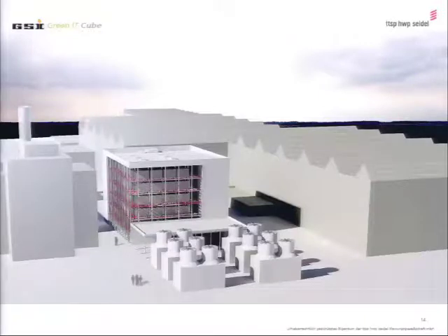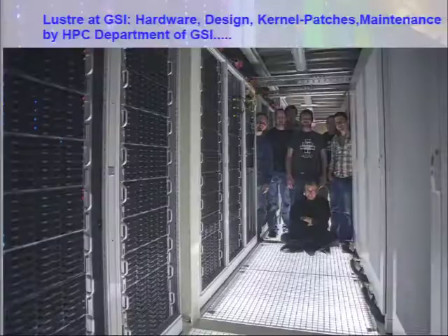So with 27 degree water going in, we have 27.5 or 27.8 degree water going out. This small temperature difference is everything we need. So we can run this quite cool, even if the summer is hot, at an extremely good PUE, and the trick is the waterfalls in combination with the cube design.